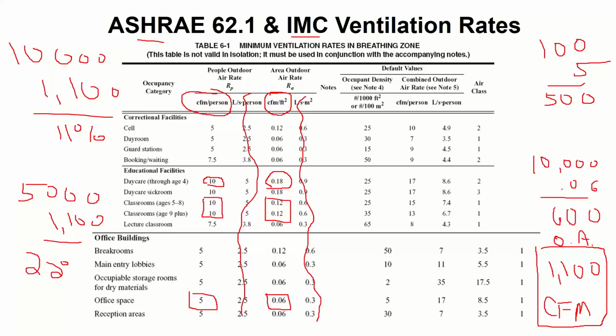So if anyone ever tells you, hey, your building should have this percent of outside air, they're absolutely totally full of crap. The percent is just something I'm giving you as an example. At no point in time should your engineer or your field technician go up to the ventilation damper and set it for a certain percent. That's just a coincidence. The percent is what? Well, it depends on how much air I had and how much of it has to come from outdoors. And that's not the same on every job.